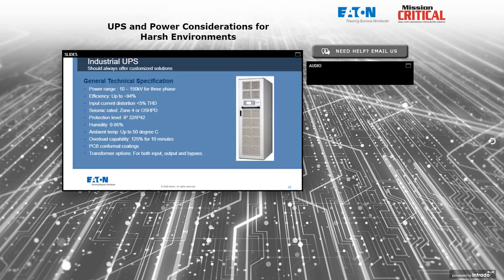The general technical specifications for mid-range size UPSs: efficiency in the mid-90s, input current distortion less than 5%, seismic rated either zone 4 or OSHPD for here in the US, cabinet construction IP32 or 42, maybe 54 for marine applications, humidity 0 to 95%, and it should also say non-condensing. That's a lot tougher in an industrial environment.